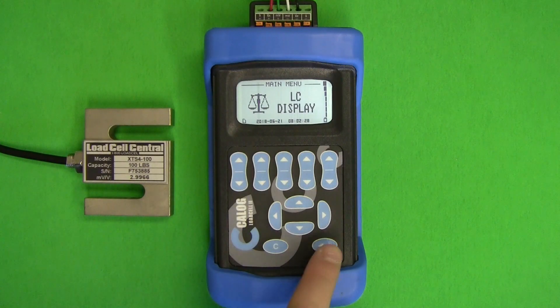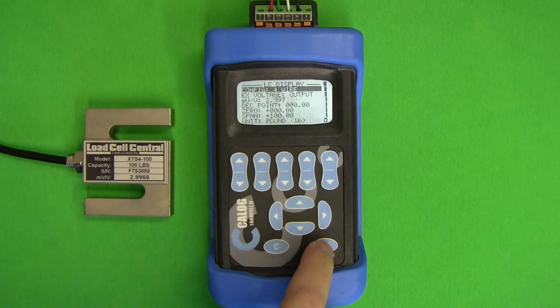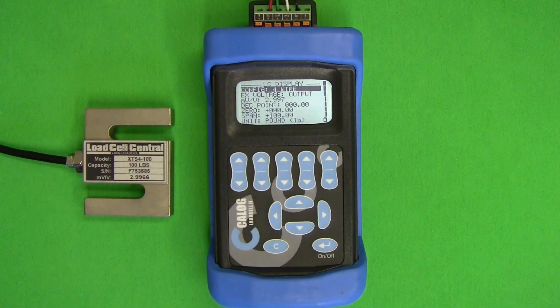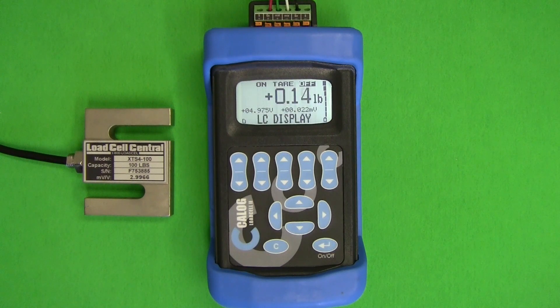The load cell display selection allows us to completely configure the Calog as a load cell indicator. In the setup screen we can set the Calog to provide a fixed 5-volt excitation. We can also set the millivolt per volt, decimal point, increments, zero, span, and force units. Filters as well as zero and span trim adjustments are also available. Once these are set we can enter the load cell display and begin using this device as an indicator.